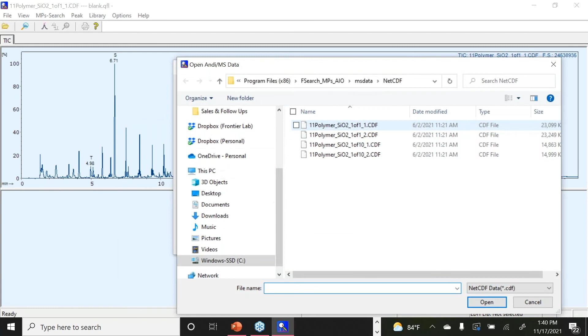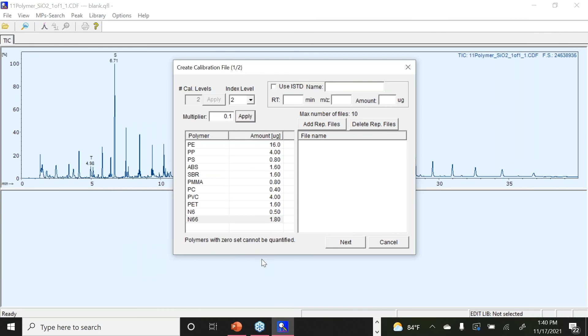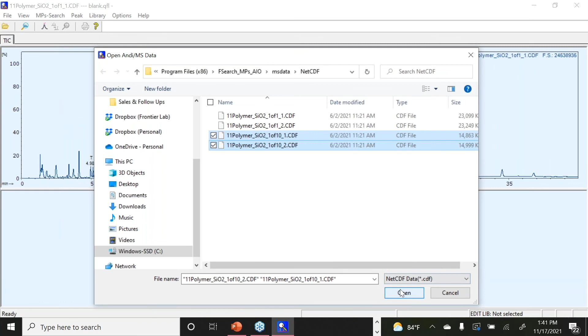So my second calibration curve, I did 1/10 of my first one. So the multiplier will be 0.1, and look at all these numbers that I originally entered for my 4 microgram. Then I did multiplier 0.1 because I did 1/10 of it. So when I apply, the system automatically calculates that for you. So all I need to do is add the other standard that I ran, twice of them, 1 of 10. So everything looks good. You could say next.